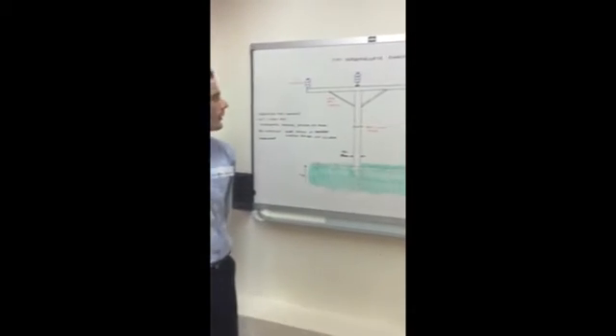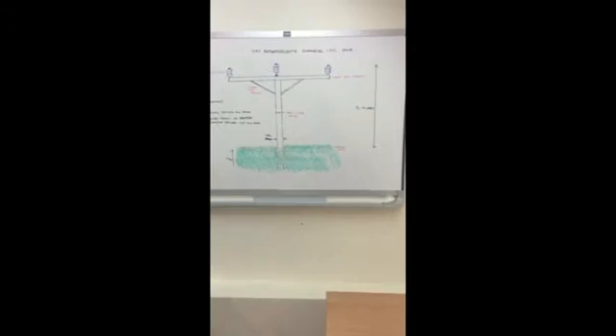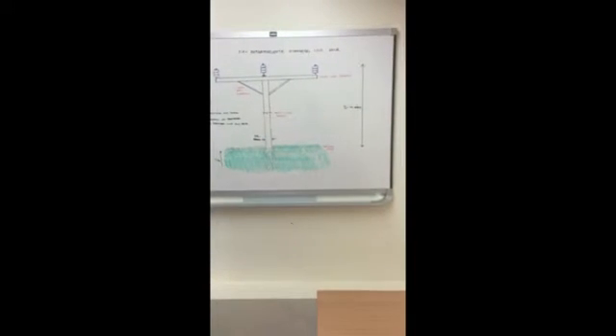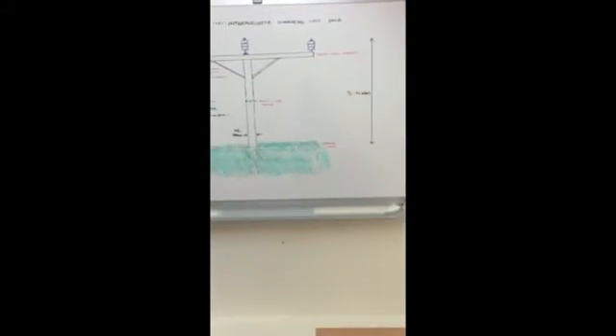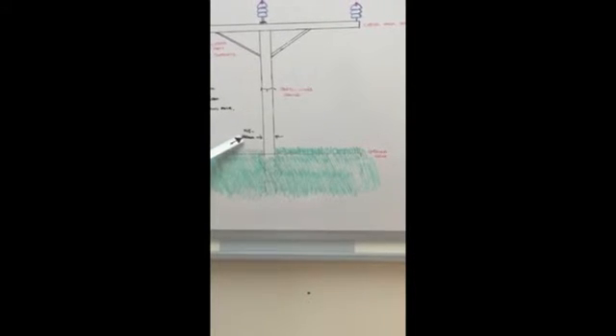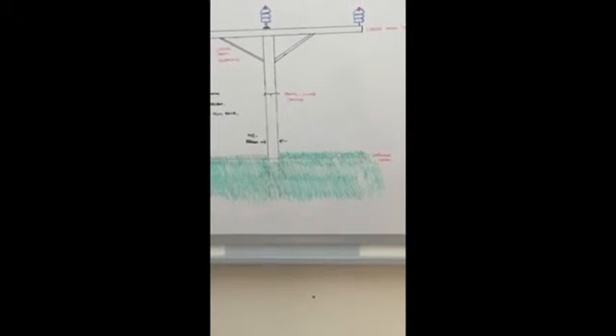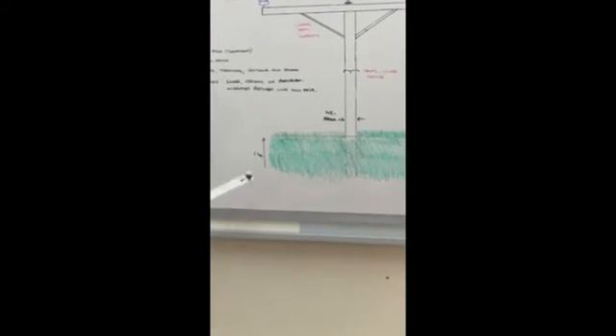As my colleague Alan has already mentioned, there are many different types of pole. Today we're going to look at an intermediate type pole. Firstly, we will look at the dimensions of a standard wooden pole. Poles vary in height between 8 and 14 metres. Depending on the height of the pole, the diameter can vary between 145 to 160 millimetres. And generally the pole will be 1.4 metres underground.